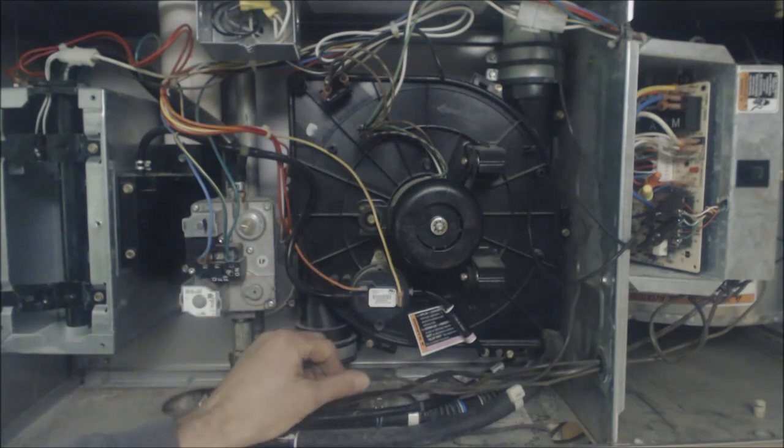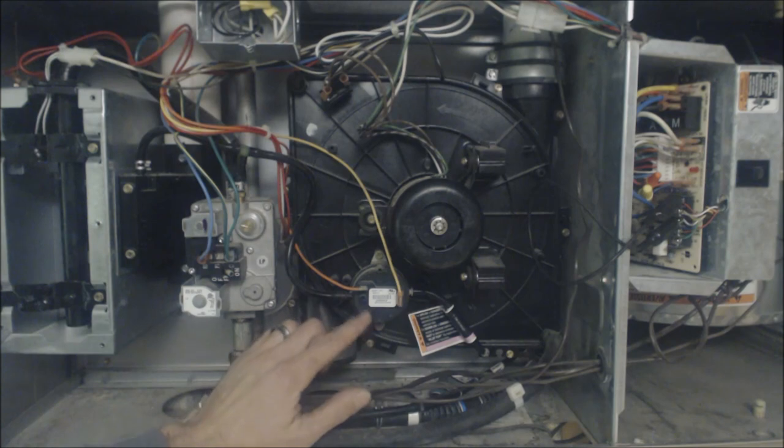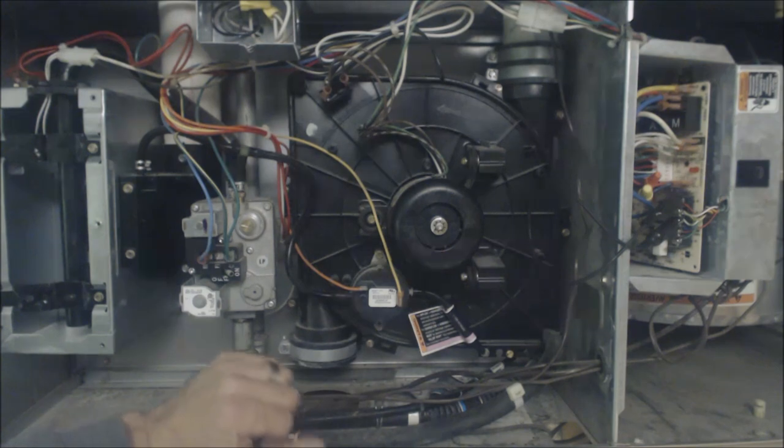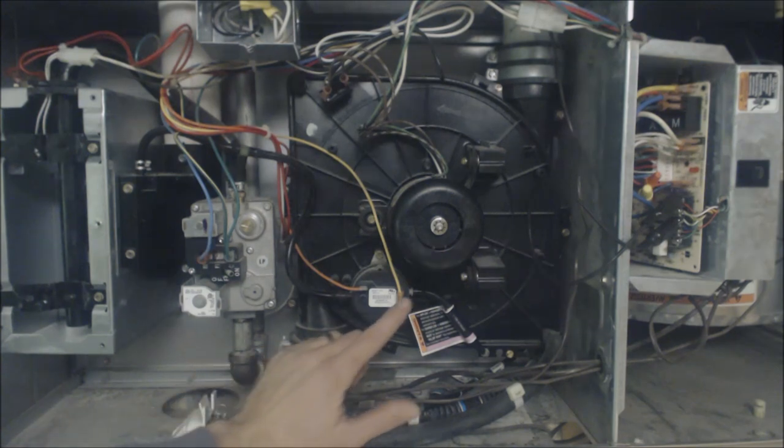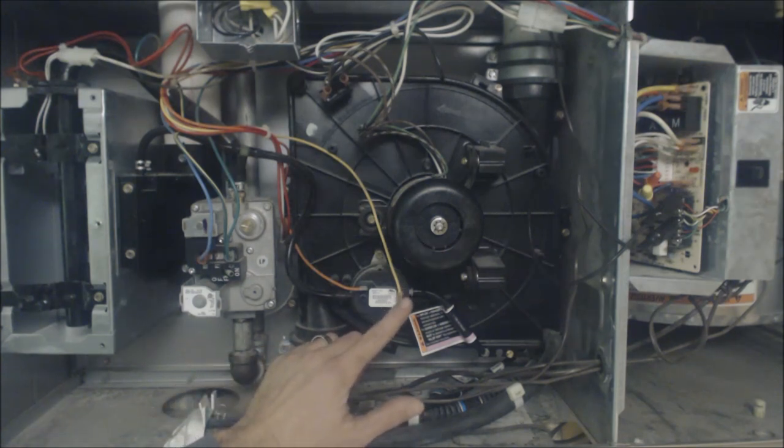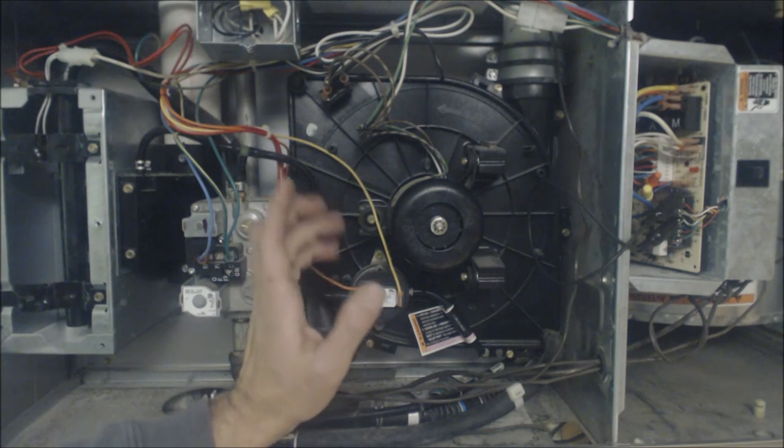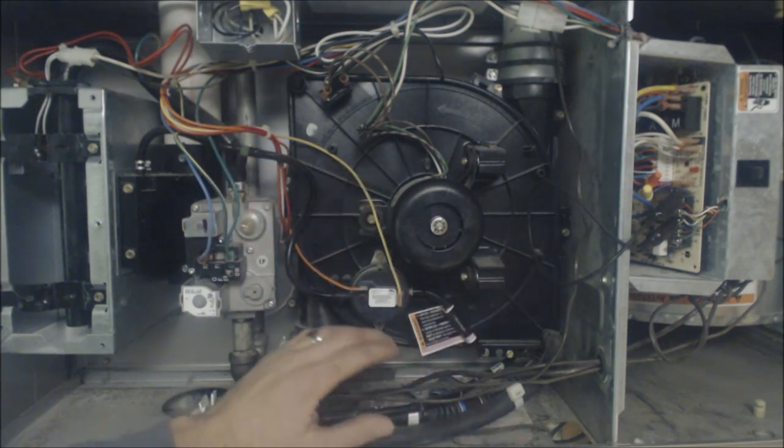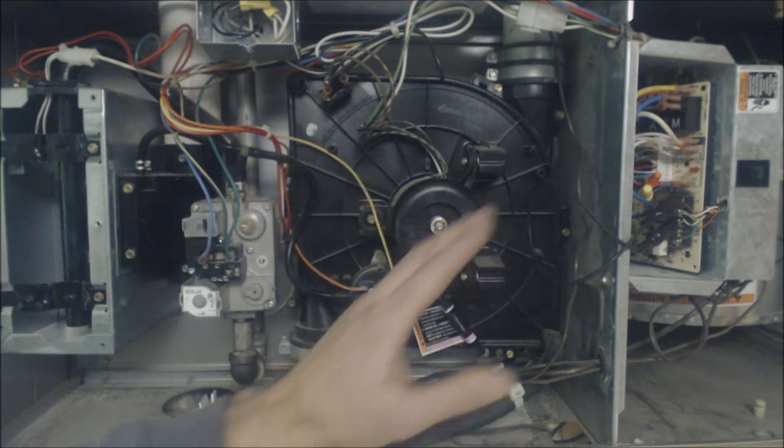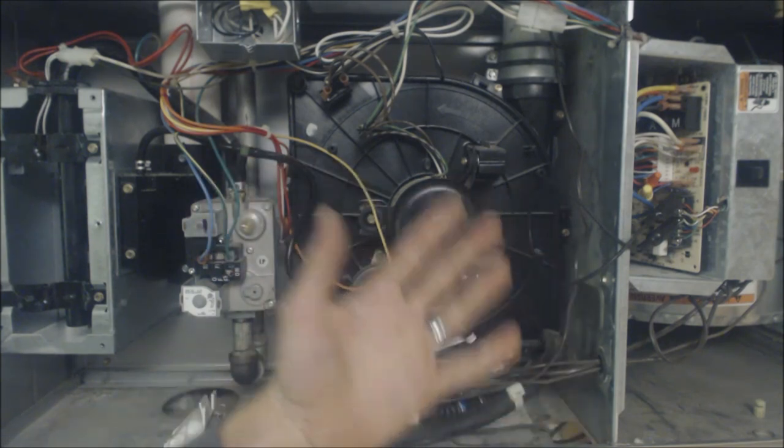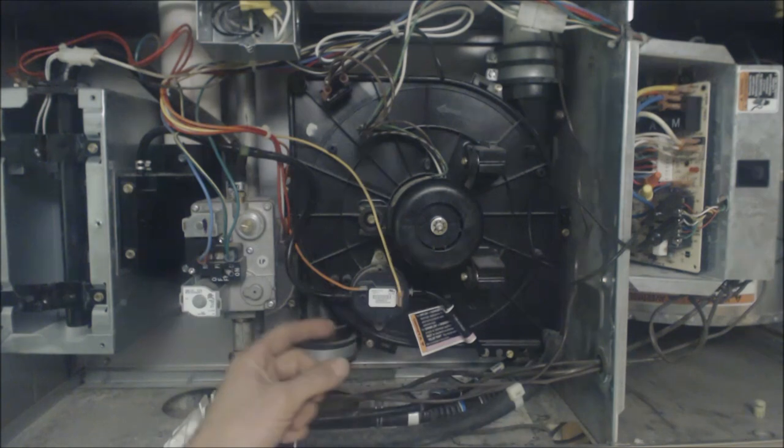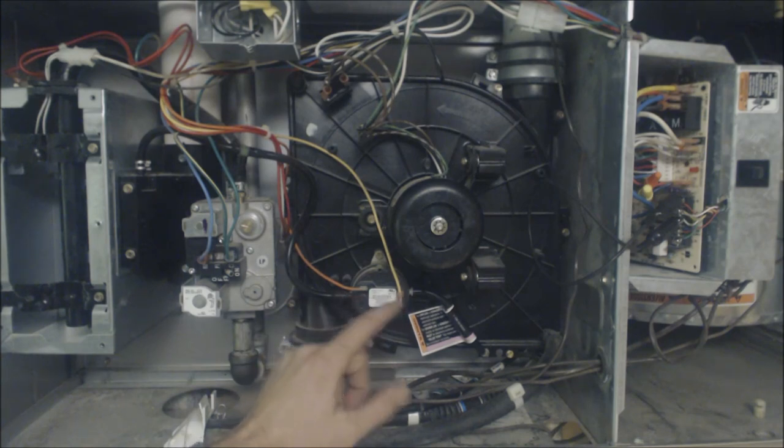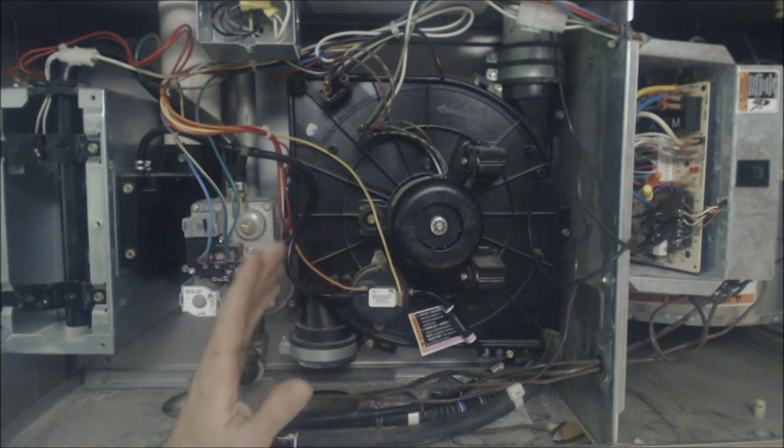There is a 24 volt signal, 24 volts comes in and it has to come through and then it goes directly back to the control board. This way the control board can give you an error code that says hey there's something wrong, it's not reading the negative pressure at the pressure switch. These wires right here do not go in series with any other wires such as the flame rollout sensor or there is a plenum heat sensor back here.